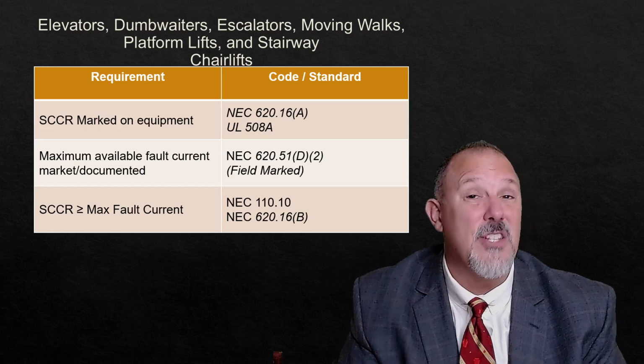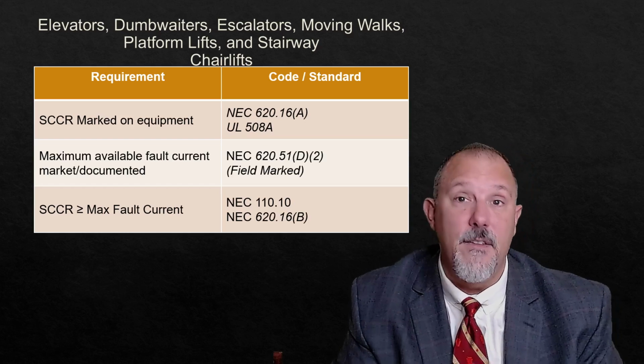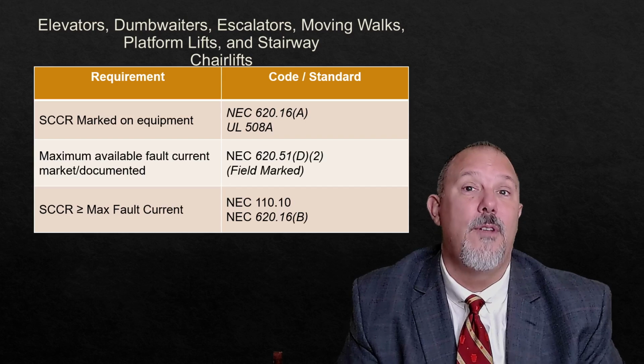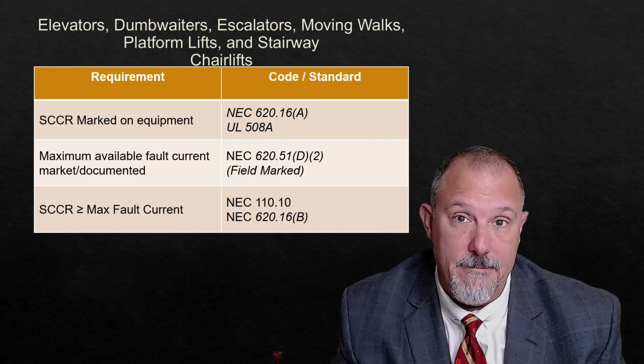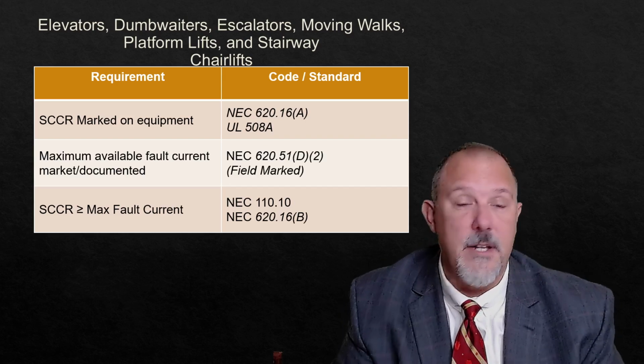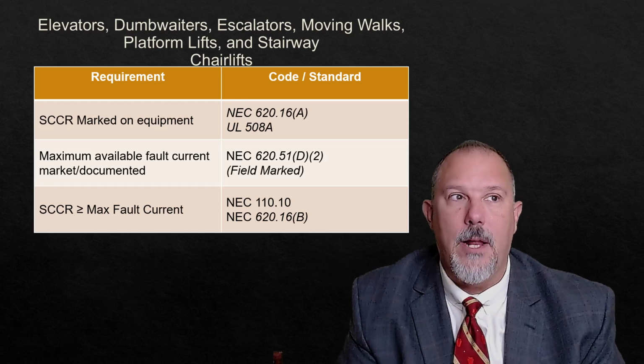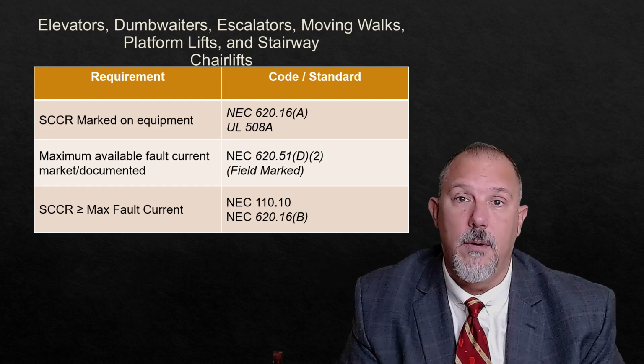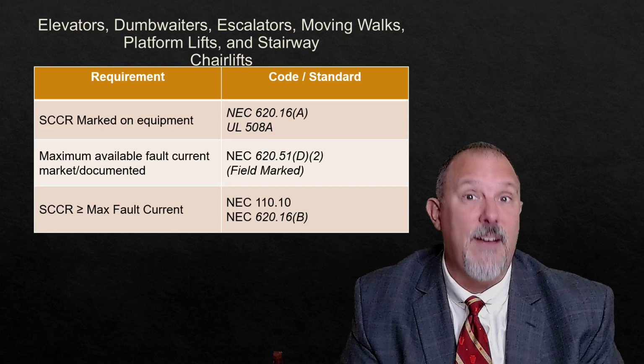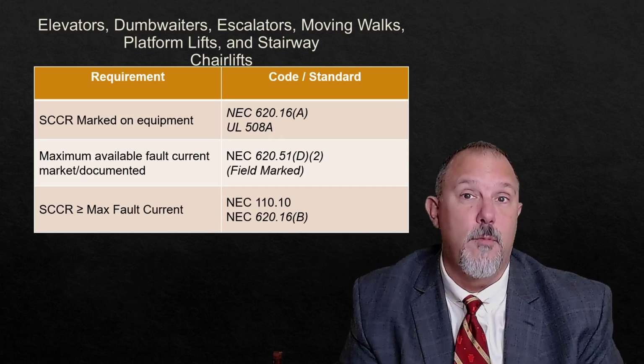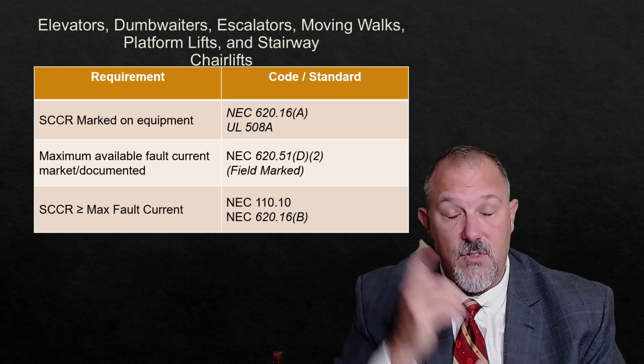And in many cases, it's hard to find, say, an elevator control panel listed greater than 10K. They'll tell you to lower the fault current. How do I lower fault current? One-to-one transformer. That really complicates things. You better have tap changers on that. You better have the room on the roof. Think about it.